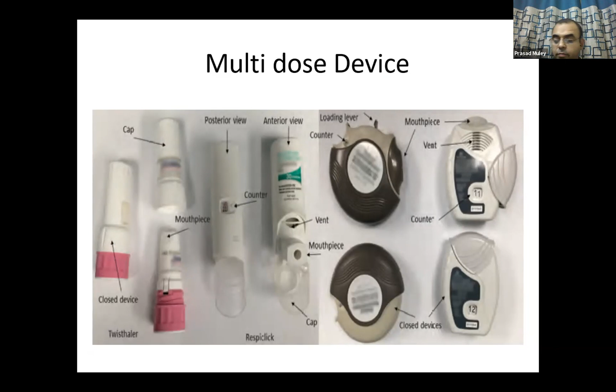Once the dose is loaded, the patient should exhale first and be careful not to breathe inside the device. Because when the patient exhales inside the device, it will humidify the capsule content or the drug. Then the next time when the child or patient tries to inhale deeply, the amount delivered or inhaled will be lesser than required. So the result will not be that good. It is better to exhale out, then put the mouthpiece inside the mouth and go for a strong inhalation, followed by holding the breath for 10 seconds, and repeat if indicated, depending upon the medication we are using.